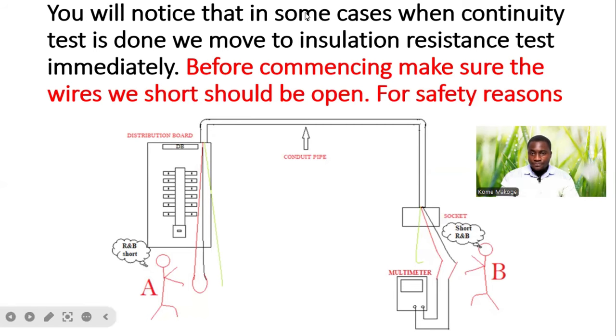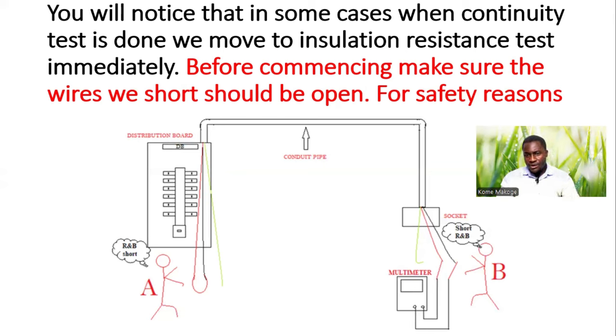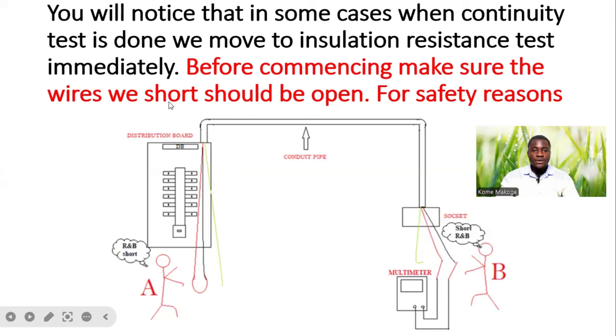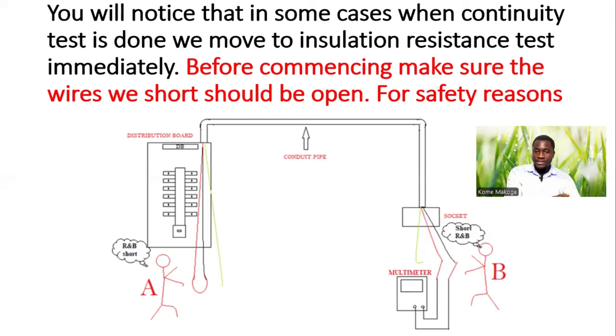In some cases when continuity test is done, we move to insulation resistance test immediately. Before commencing the megger test, make sure the wires that were shorted are now open. Because while carrying out continuity test, we have to short one end and then test the other. If we are going straight to perform insulation resistance tests, we have to ensure that we open the end that was shorted previously while carrying out continuity test.